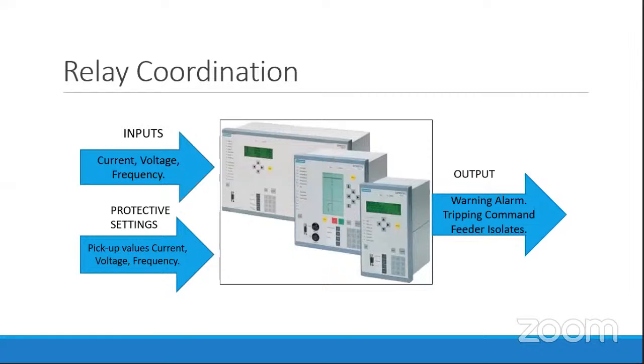The protective relays have certain inputs: current, frequency, and voltage, as I said. Now we can set the protection settings, like overcurrent protection, short circuit fault protection, undervoltage and overvoltage philosophy, and overfrequency and underfrequency philosophy. We need to provide protective settings such that if any quantity, current or voltage, goes beyond the set parameter, then it should pick up and raise a tripping command.